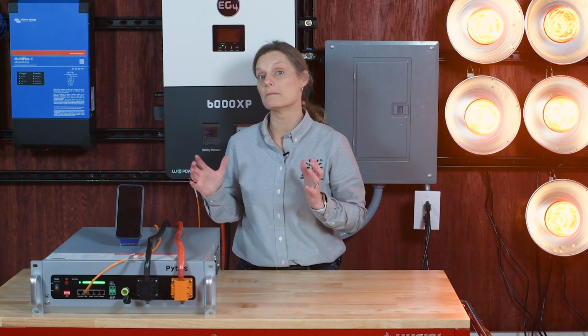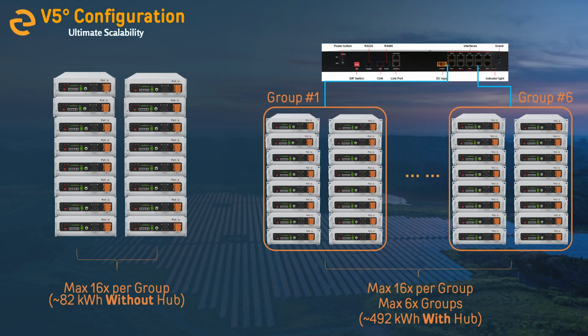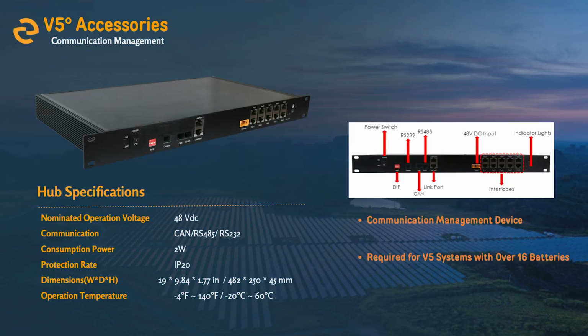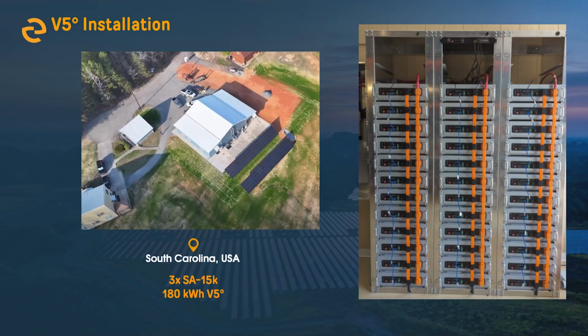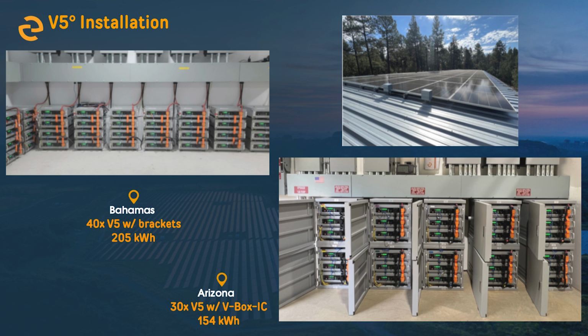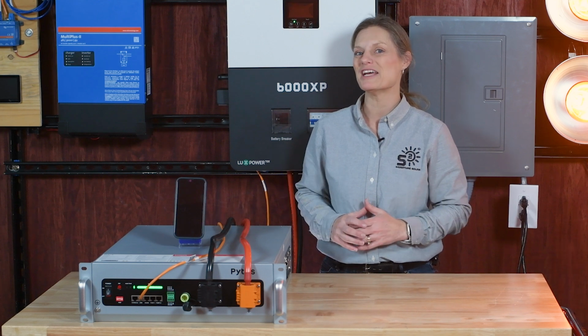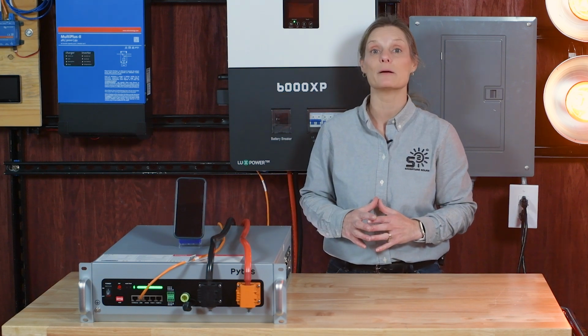One of those is its amazing scalability. You can parallel up to 16 of these batteries in a single group. With a hub, you can expand that to 6 groups, totaling 96 batteries. That's over 491.52 kilowatt hours of storage. This makes the V5 suitable for small residential setups as well as large commercial projects where you might need a lot more power storage. If you're an installer, you'll appreciate how the V5 simplifies the setup process.